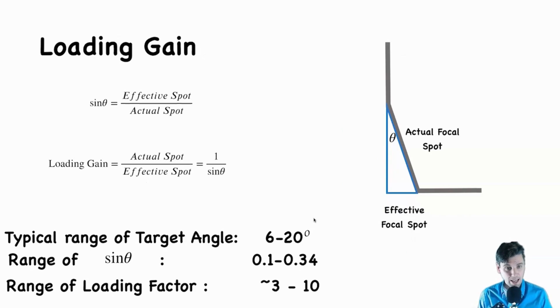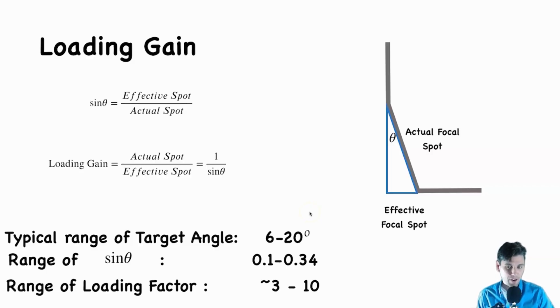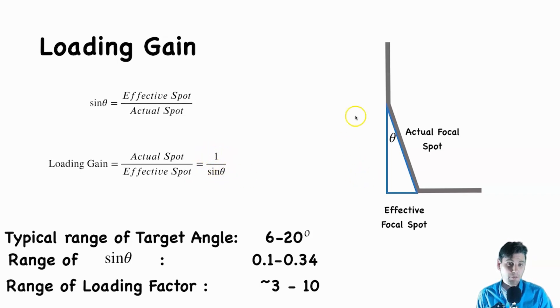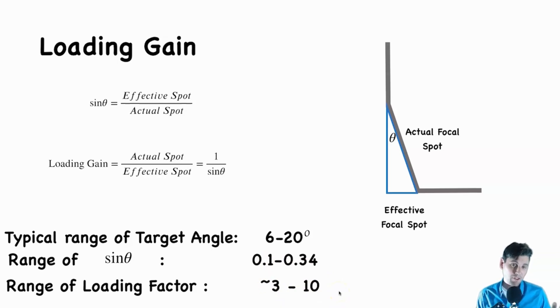We also talk about that in terms of the loading gain. The loading gain means we're able to deposit more energy without melting the x-ray tube. Using the same equation but solving for a different variable, the loading gain is the actual spot divided by the effective spot, which equals one over sine of theta. Since sine of theta varies from 0.1 to 0.34, one over sine of theta varies from about 3 to about 10. So the line focus principle gets us between a factor of 3 and a factor of 10, depending on the target angle.